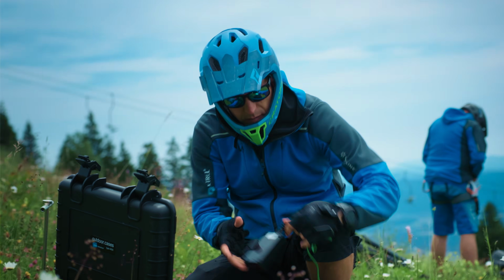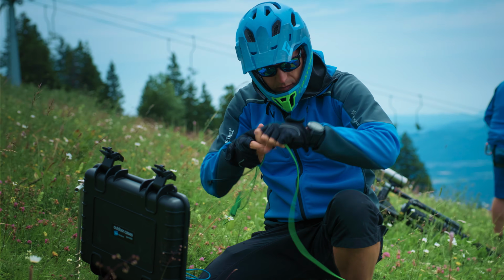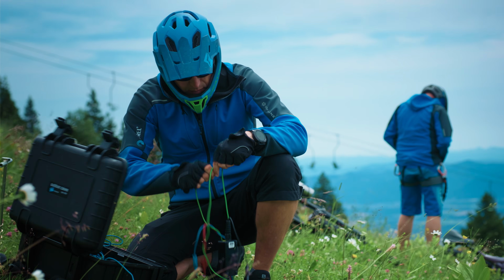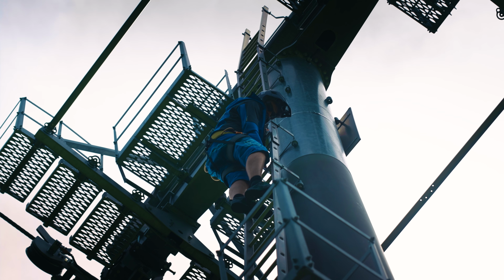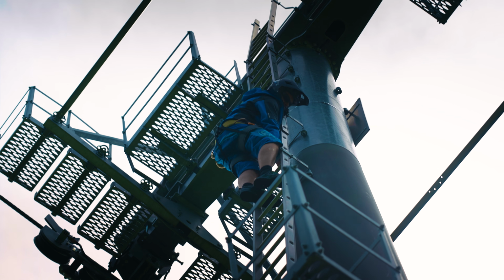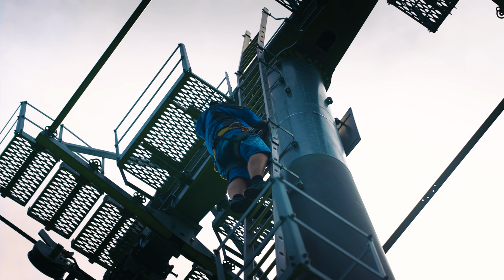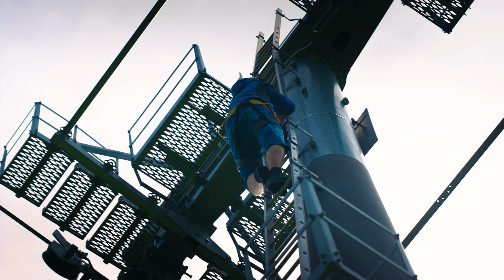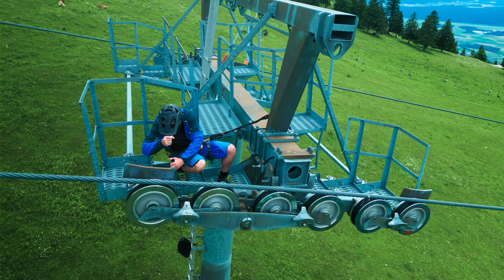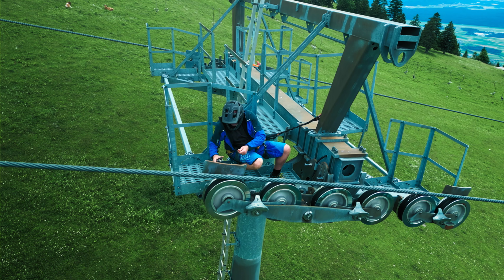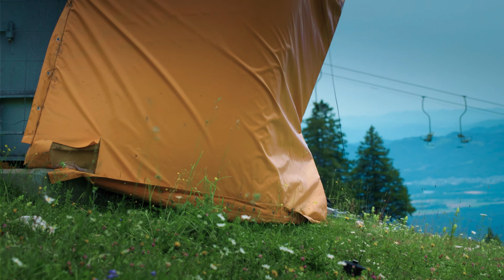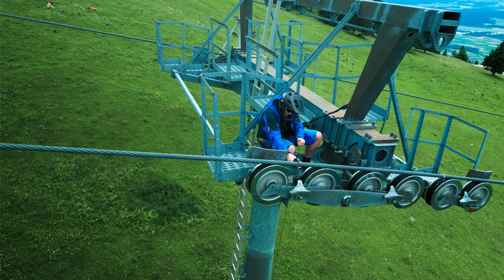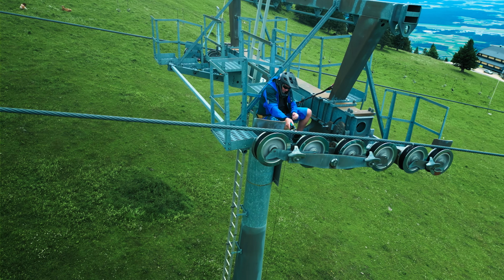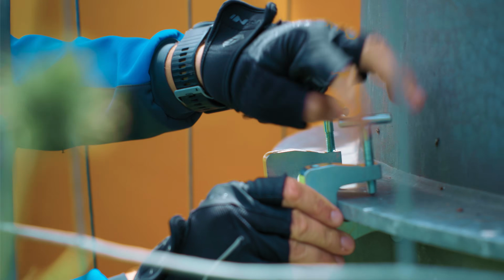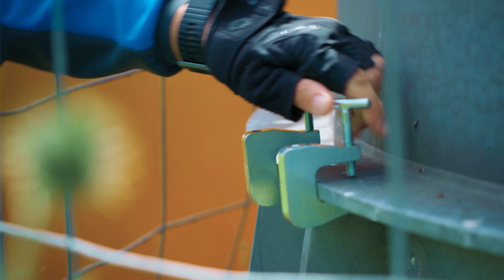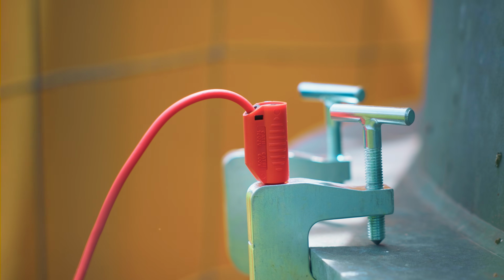While one operator prepares the generator, test plates, test leads, and connections for the MI3288 tester, the other climbs the tower to attach the measuring lead to the carrying cable. The test lead from the top of the tower is lowered to the inspector, who connects the MI3288 tester between the cable and the tower. Two G-clamps are used to secure the measurement leads, and the test begins.